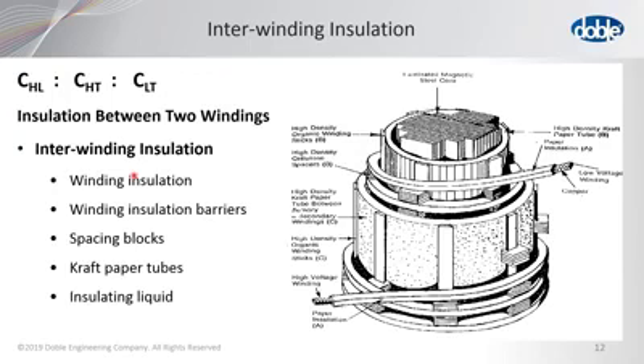They may find a problem that the AC test might not. I'm identifying that because this is normally a DC test, or can be a DC test, right? And it may energize the insulation differently. But if that winding insulation test is an AC test, more than likely it's going to show the same things. One thing that I want to be very clear about is that with insulation resistance tests done with a DC test, even the manufacturer of that equipment usually says that a PI for that type of insulation is not going to show any significant issue. Even if there's something wrong with the insulation, the PI test will probably not identify it.